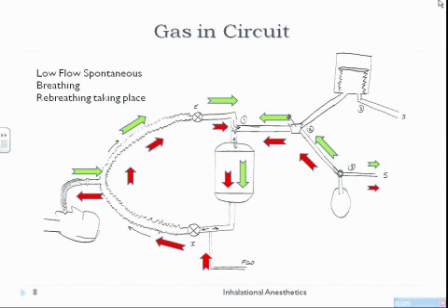What's here? That's your CO2 absorber. That's what eliminates the CO2. If you didn't have the CO2 absorber, then you wouldn't want the person to rebreathe at all, and you'd have to increase your flow rates to double the minute ventilation to assure that didn't take place. But that's very wasteful of gas, because you're taking all the anesthetic gas and not rebreathing any of it; it's all going out the scavenger. That's why we have the absorber. Does that make sense now?